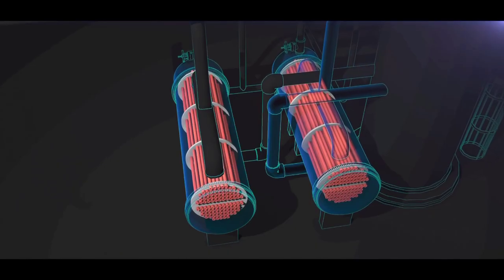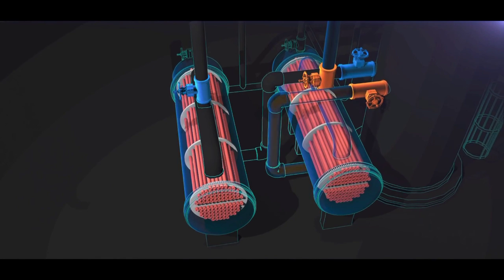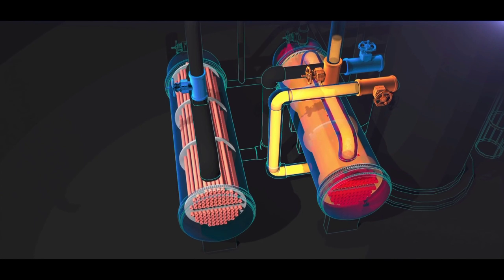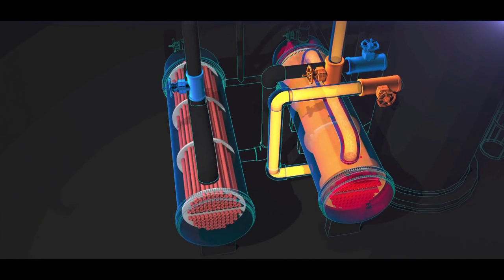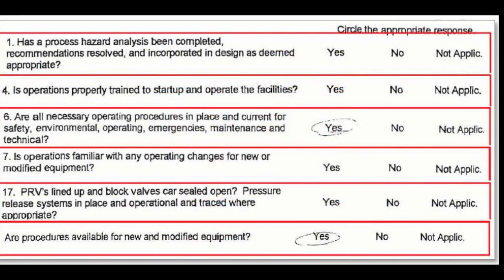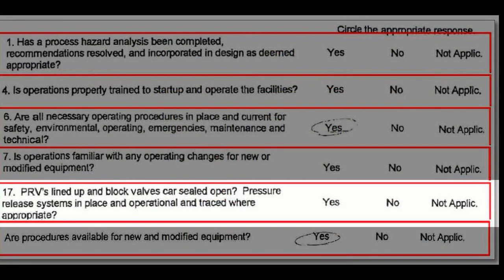After the 2001 reboiler valve installation, Williams also performed a pre-startup safety review as required by regulations. But the CSB found that Williams reviewers did not respond to key process safety questions on the form. One of those questions asked, 'Are pressure relief systems in place and operational?' That answer was left blank. Even though the pre-startup safety review document was incomplete and there were unanswered questions, management approved the form, and the reboilers were put into service without adequate overpressure protection.